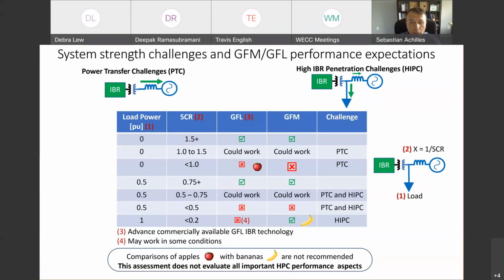So in a way, one of the main points here is that when we look at fault behavior and fault recovery, grid forming can operate for short circuit ratio 0, but only when you have a local load and power transfer is not an issue. If the system or application has a challenge of transferring power through a long corridor, then potentially grid following and grid forming may have similar behavior, with the advantage to grid following that it has many more years of design and maturity.